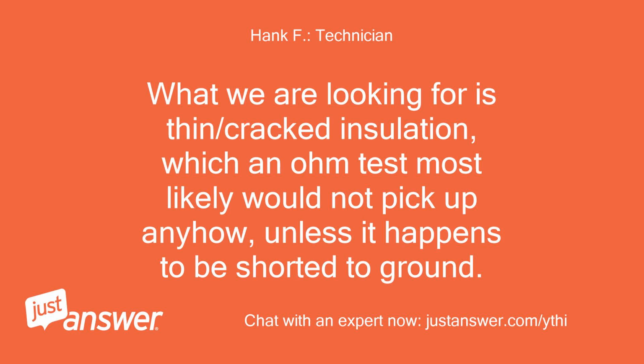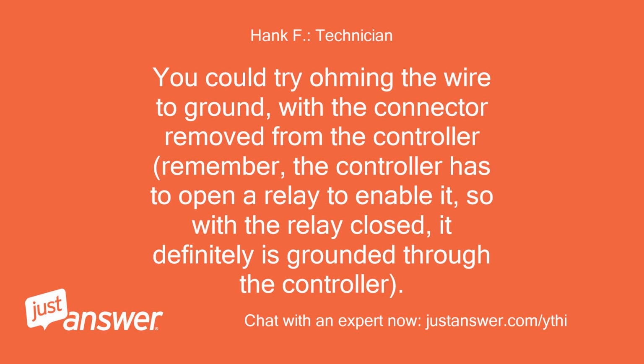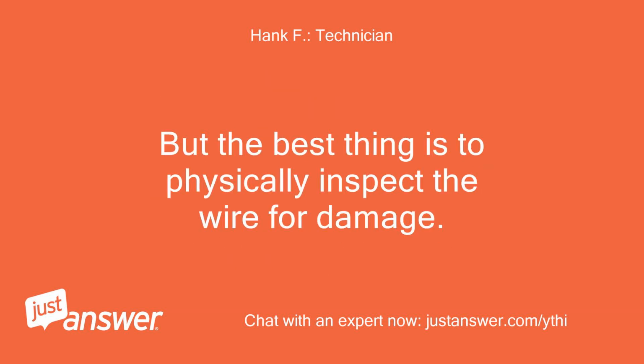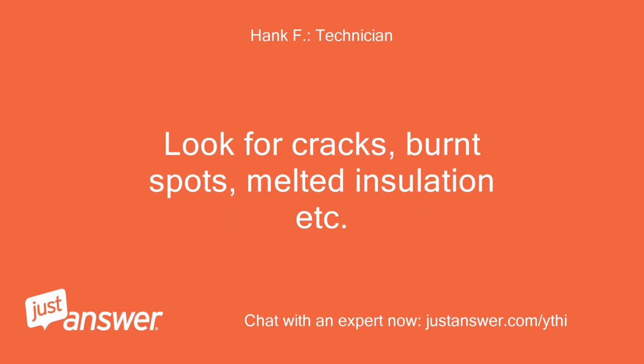What we are looking for is thin/cracked insulation, which an ohm test most likely would not pick up anyhow, unless it happens to be shorted to ground. You could try ohming the wire to ground, with the connector removed from the controller. Remember, the controller has to open a relay to enable it, so with the relay closed, it definitely is grounded through the controller. But the best thing is to physically inspect the wire for damage. Look for cracks, burnt spots, melted insulation, etc.